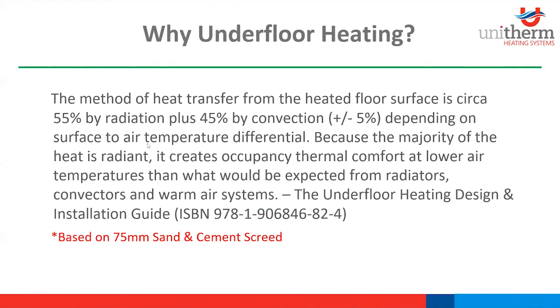So a bit here taken from the underfloor heating design and installation guide. Now this is based on a 75mm sand and cement screed, which is pretty normal for ground floor screed installation. The method of heat transfer from the heated floor surface is circa 55% by radiation plus 45% by convection, plus or minus 5%, depending on surface to air temperature differential. Because the majority of the heat is radiant, it creates occupancy thermal comfort at lower air temperatures than would be expected from radiators, convectors, and warm air systems. They were just saying that by the thermal mass radiating, we can expect occupancy thermal comfort at lower air temperatures. I just wanted to take note of that, and we'll get on with this then.